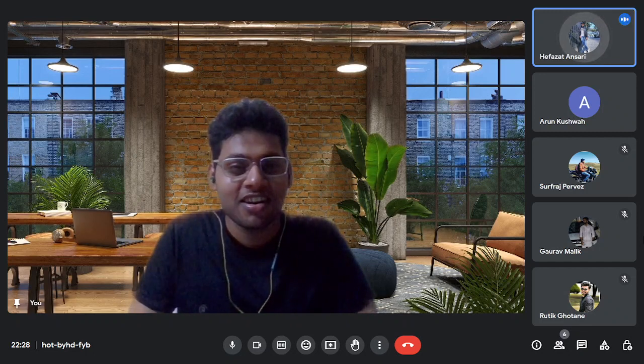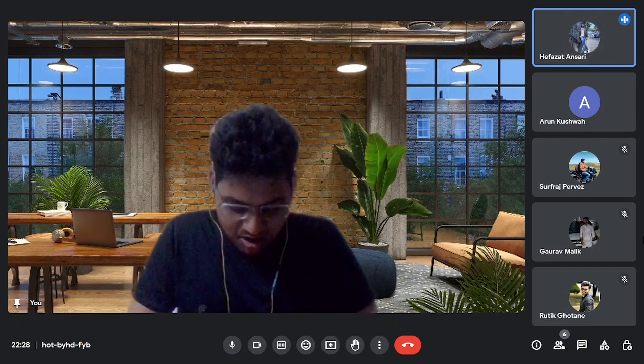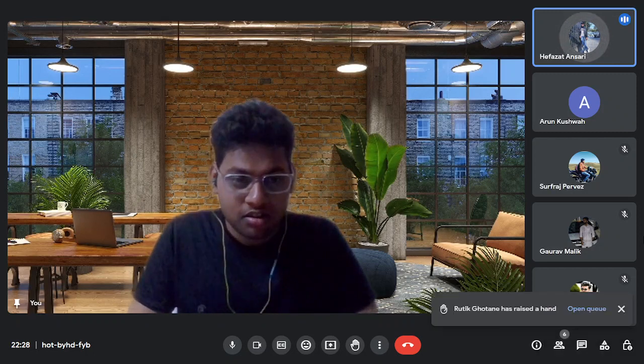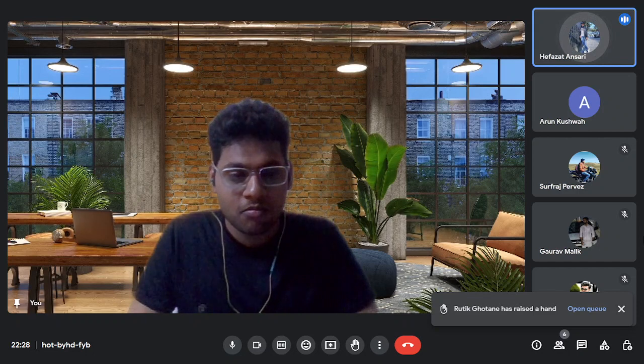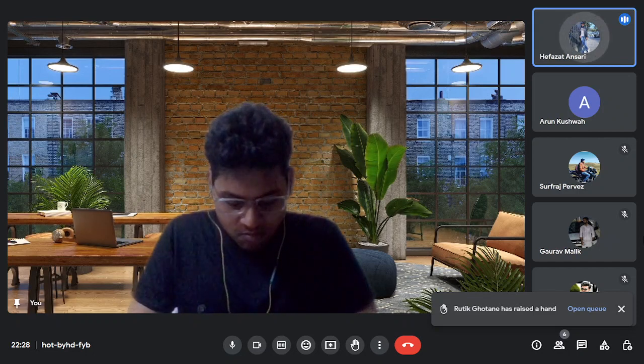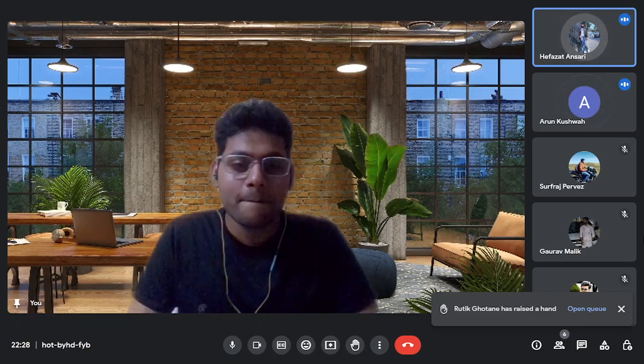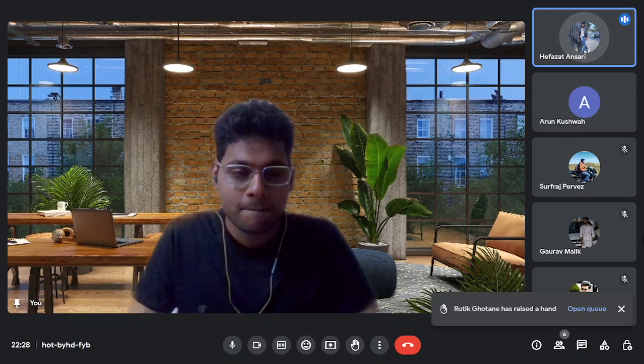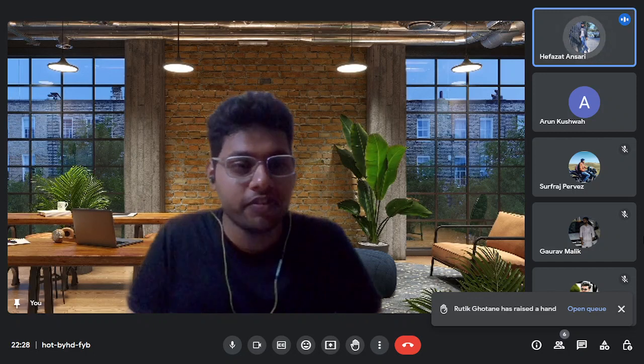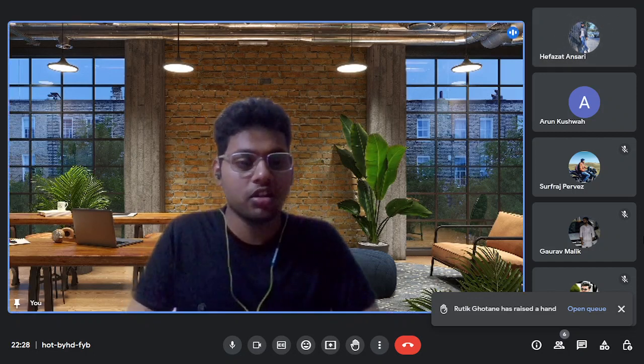As we know, a centrifugal pump is a non-positive displacement pump. It is generally used for high discharge and not for high pressure. So it will not generate such an amount of pressure which will damage its pipeline. That's why we don't have any relief valve. Yeah, perfect. Ruthik, you also try.